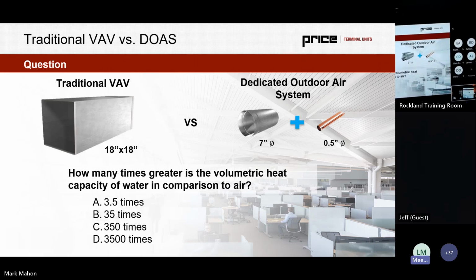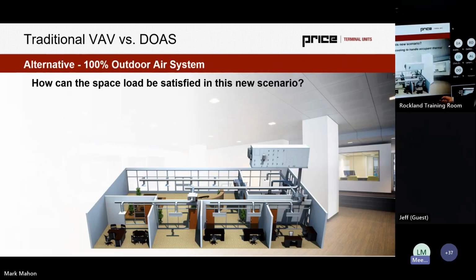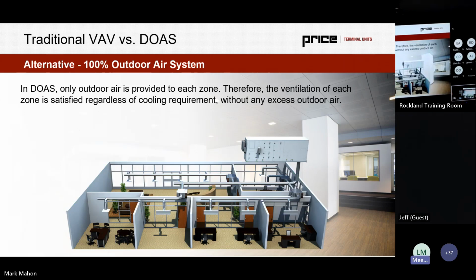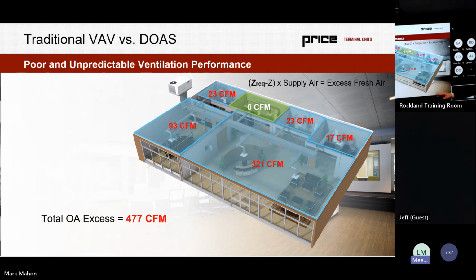Of course, it also depends on the classifications of air quality you need. So when we look at a school environment that maybe has a cafeteria, which also could have very high air requirements, that can't get mixed back into the space because it's a class 2 type air, whereas class 1 is our occupied spaces like our classrooms. So some air still usually in the system is going to get exhausted out unless it has its own designated air handler. And so there's a lot of different philosophies. What we can do with that excess air, there's further productivity we can add to this outdoor air excess that can be reutilized in the system. There's many approaches that we can do.